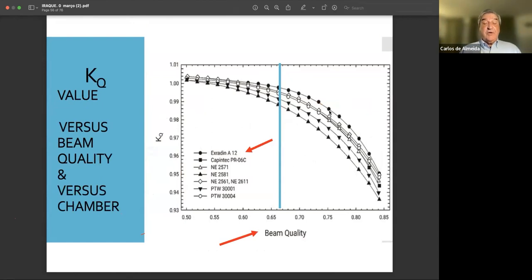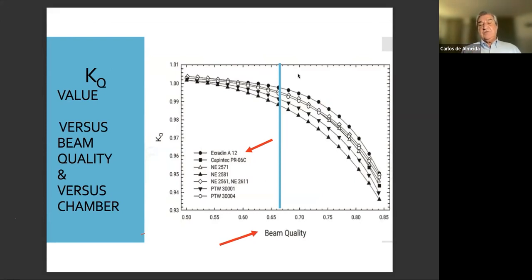You should be careful, because the KQ value depends not only on the beam quality. Here, for instance, this blue line is roughly the beam quality of a 6 MeV photon beam, but it depends on the chamber that you're using. You see, it could be a 2-3% difference from a PTW chamber to an Exradin, for instance. Why is that? Because every chamber has a different constitution, different materials in the wall, different materials in the electrode. And going back to that equation, the mass energy absorption coefficient differs for each of these. So the interactions are different, the absorption is different, the scattering is different. So you must know exactly what the KQ value is for your chamber, for the quality of your beam.